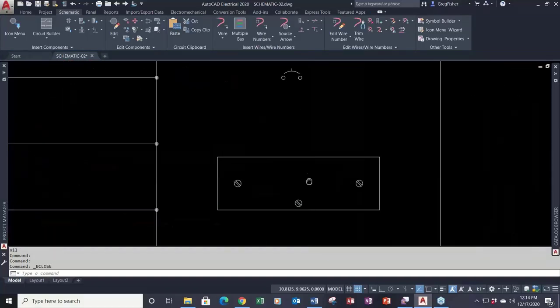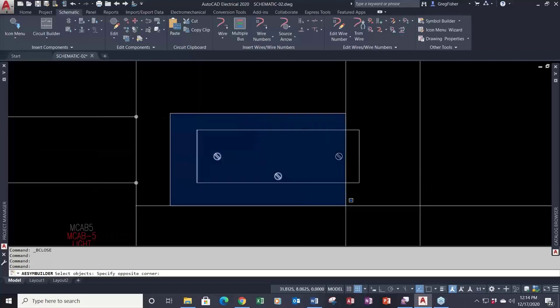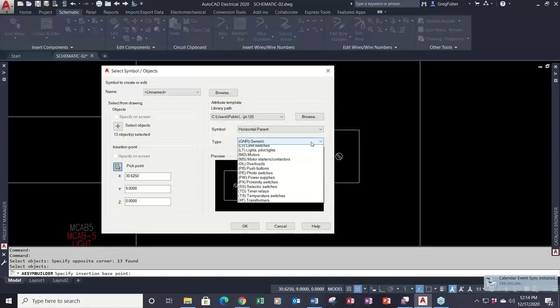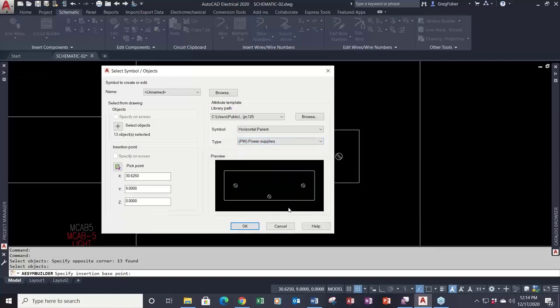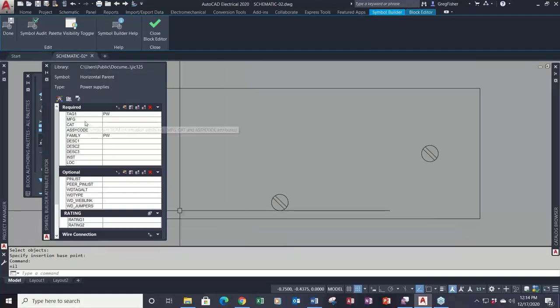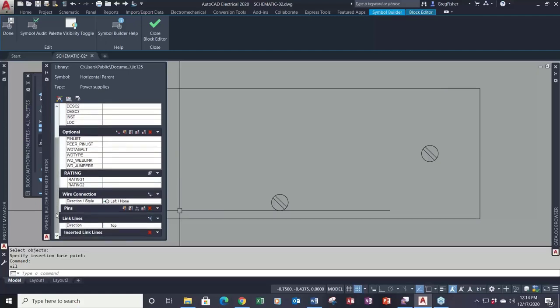If I were creating a power supply, I select my graphics, pick a base point, and choose power supply. Notice the attributes are different — there is no cross-reference attribute, because it assumes you're not going to create a parent-child relationship with the power supply. There are also some optional attributes included, like pin list attributes, that you can use on a power supply.